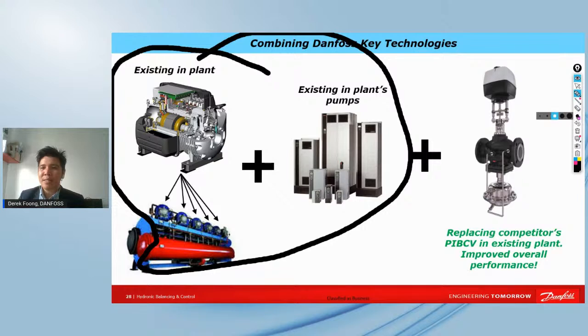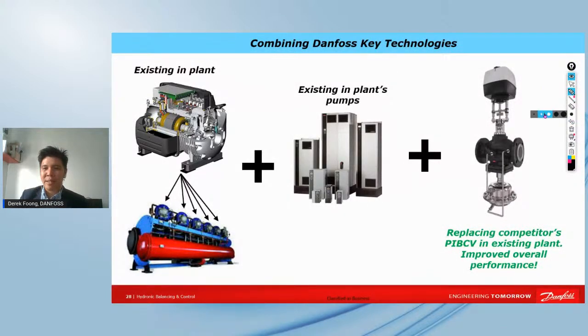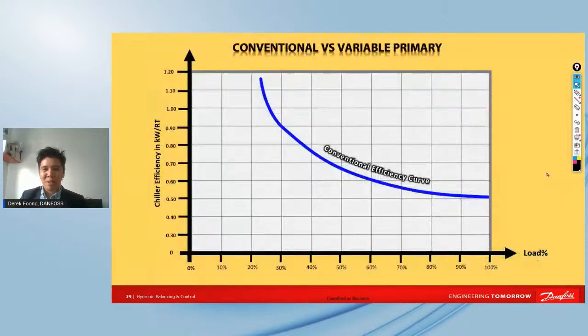But the thing is that the most underestimated part is always the hydronic control and balancing. And most people think that valves do not play a major role because they are thought of as peanuts in the system, because they are a lot smaller than heavy equipment, right? But allow me to tell you this, they are not peanuts that don't deliver significant performance. So if we talk about variable speed chillers, now we are moving from pumps to chillers.